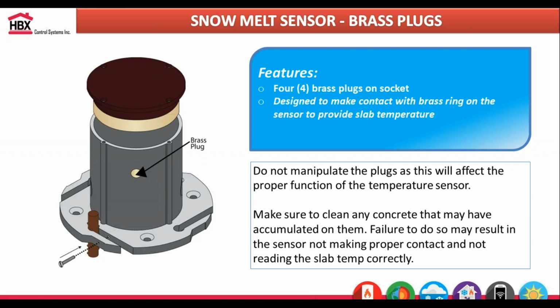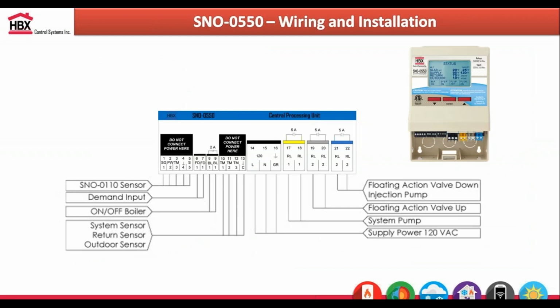So if you're ever installing this for the first time and getting an off reading, it's most likely that when they were pouring concrete, some concrete or even mud got into the socket, and it's just not making proper contact with that brass ring and those brass plugs. For those scenarios, just take out the sensor. It's just 4 screws to take it out. Take that out, give it a wipe down, put it back in, and you'll usually get a normal temperature reading.